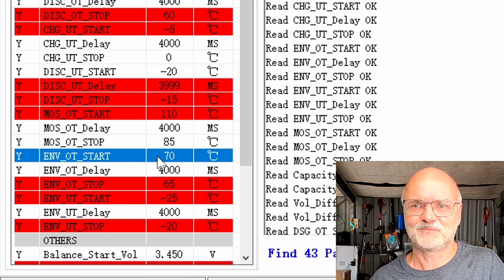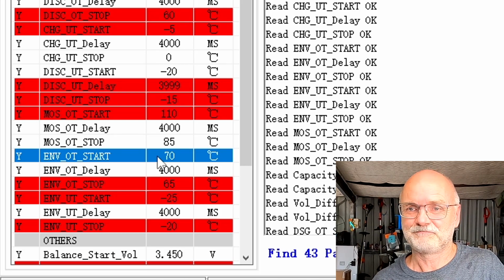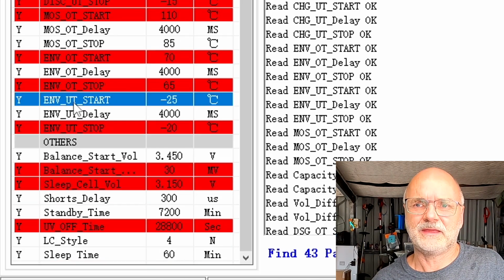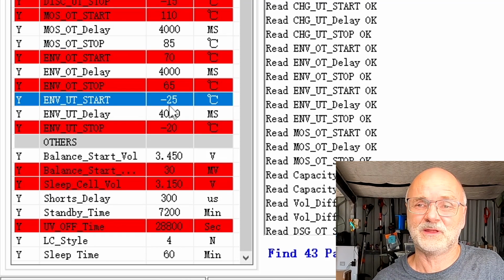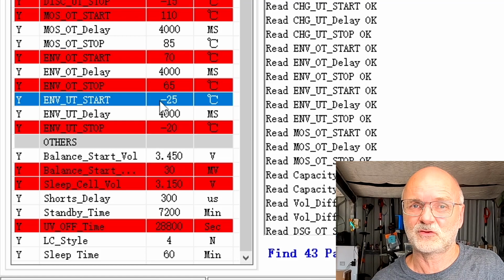And again, 70 degrees, far too hot for my taste. You won't be able to touch the case anymore. Then we've got an ambient under temperature protection of -25. I'm not sure what that actually does. Does it stop charging and discharging at the same time? Well, if so, it is far too low. It should be at +5 degrees or something then.